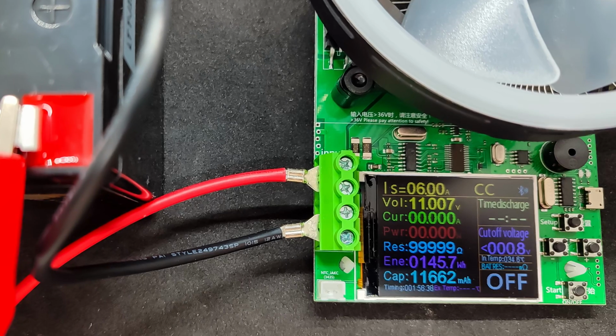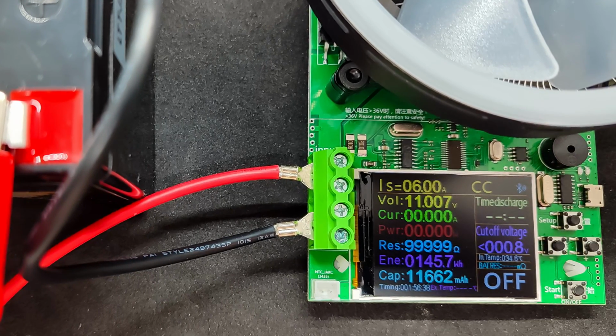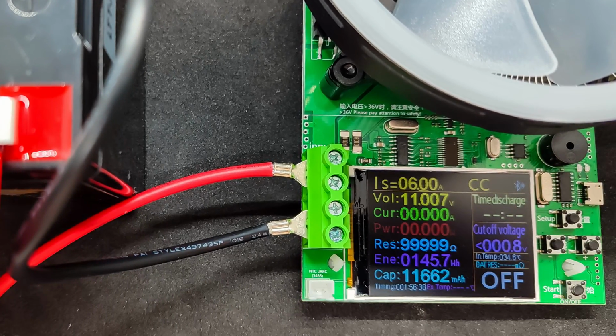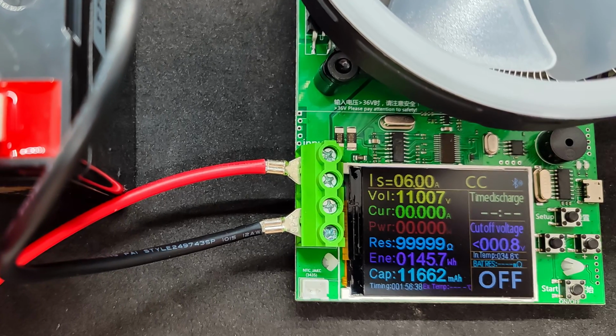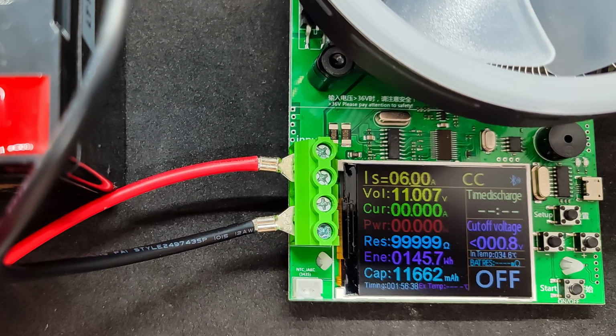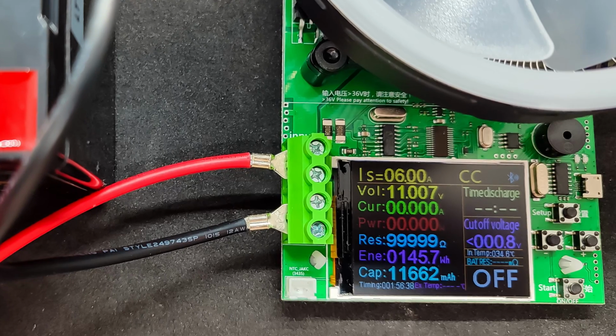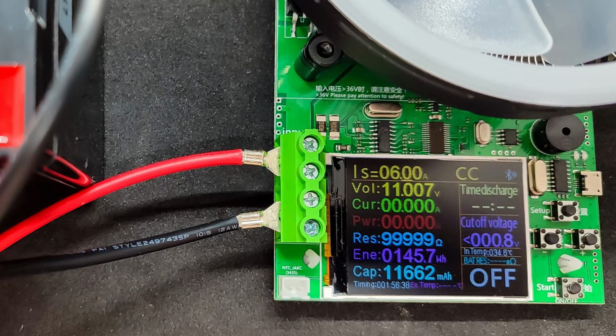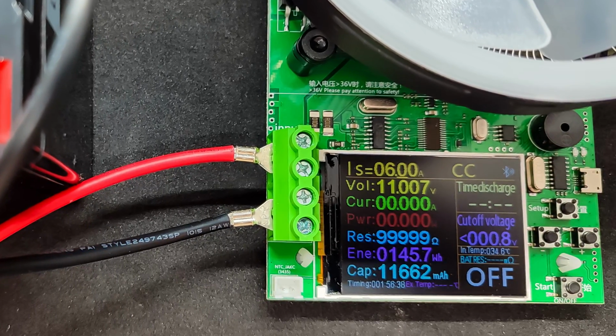In this photo, you can see that the battery voltage rose to 11 volts after the load was disconnected. As one could understand from the instructions, the BMS should have disconnected the battery cells at a voltage of 11.2 volts. But this did not happen. Is this good or bad?